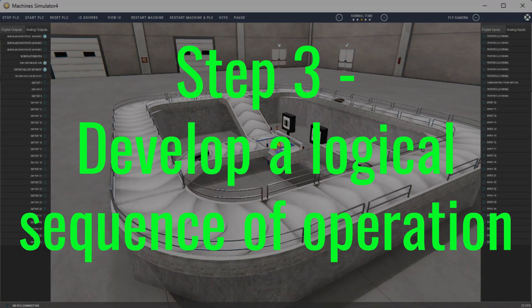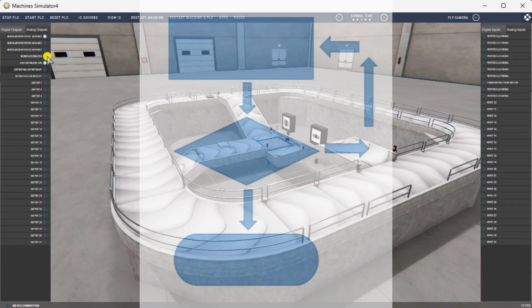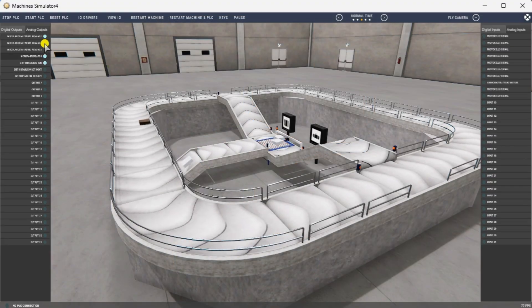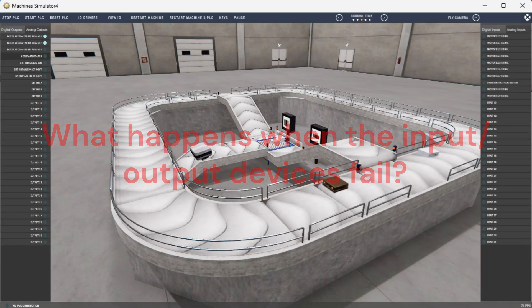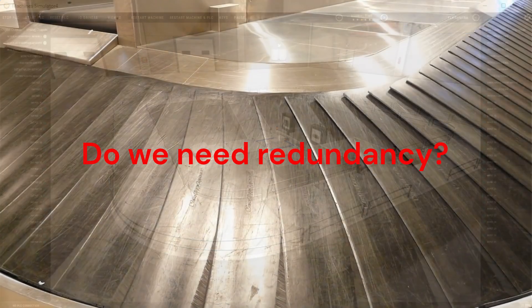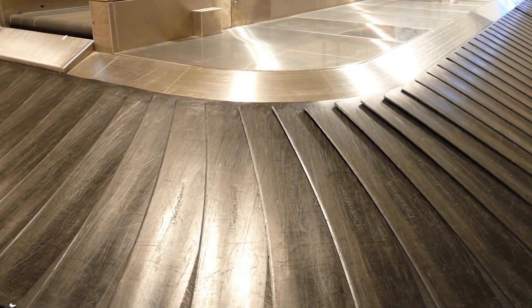Step 3: Develop a logical sequence of operation. A flowchart or sequence table is used to thoroughly understand the process that needs to be controlled. It must also answer questions such as: What happens when electrical power and pneumatic air is lost? Do we need redundancy? This step saves you a lot of work by helping you understand everything about the operation. It will help prevent you from continually rewriting the PLC program logic. Knowing all of these answers up front is vital in developing the PLC program.